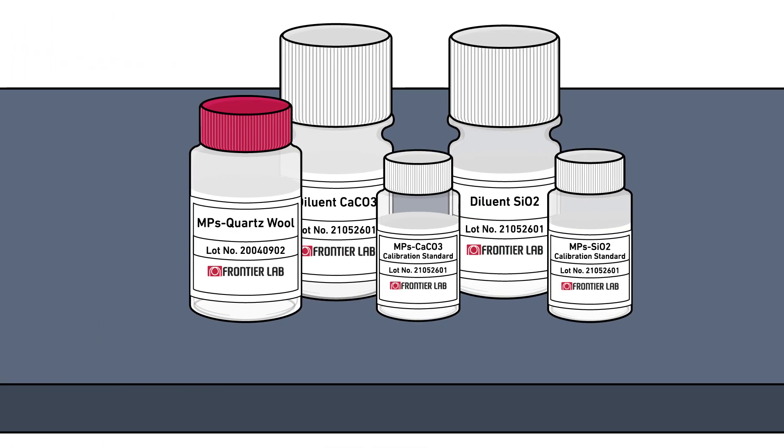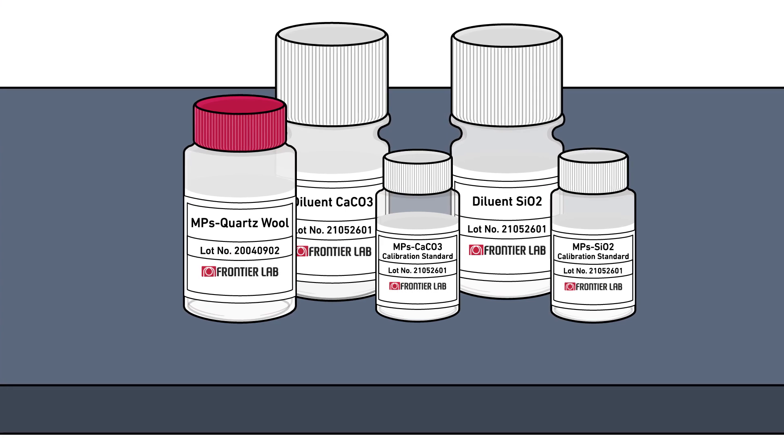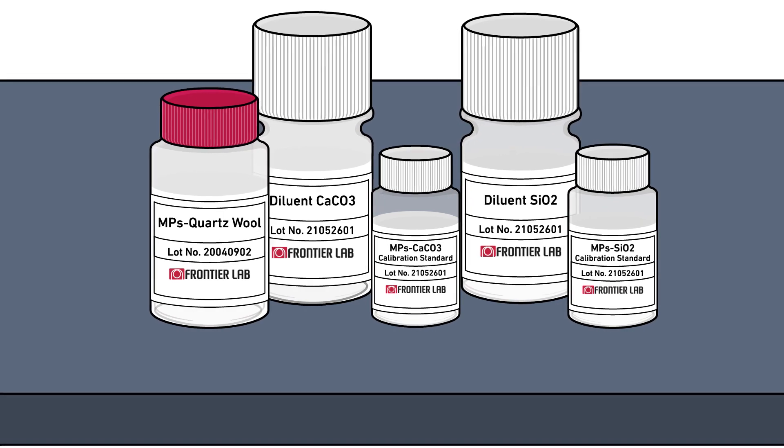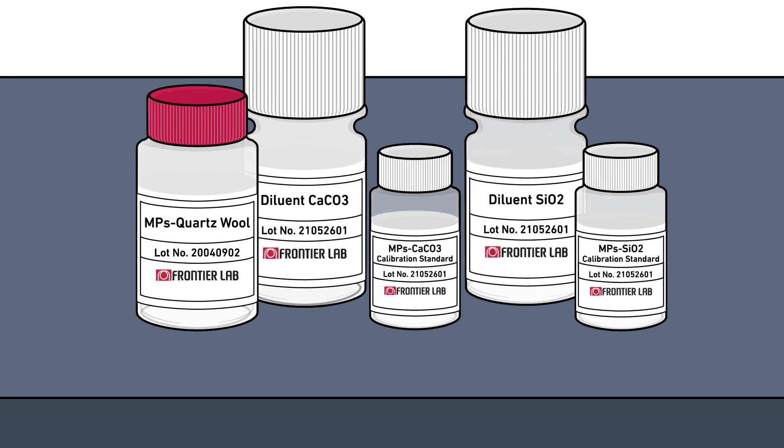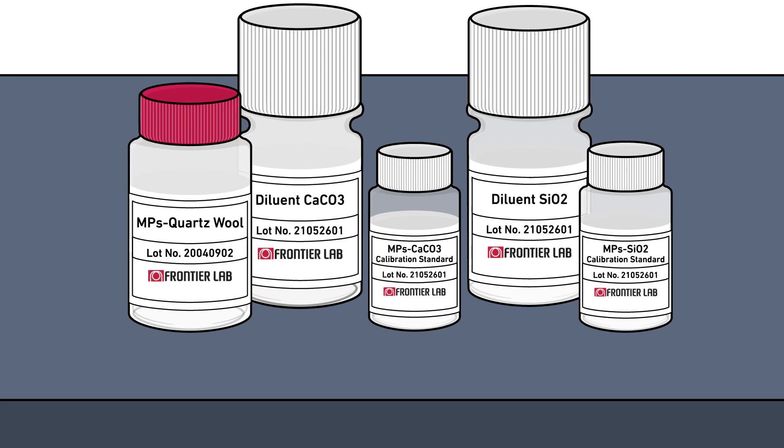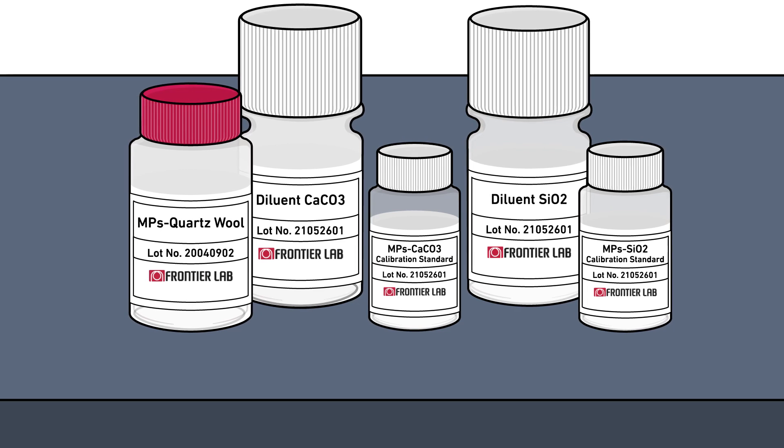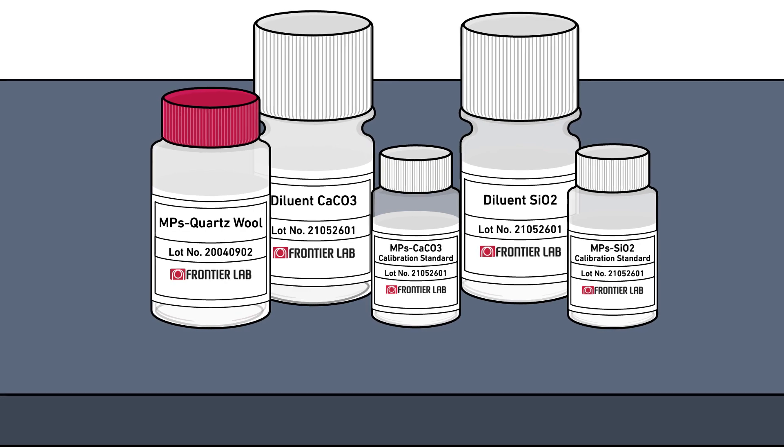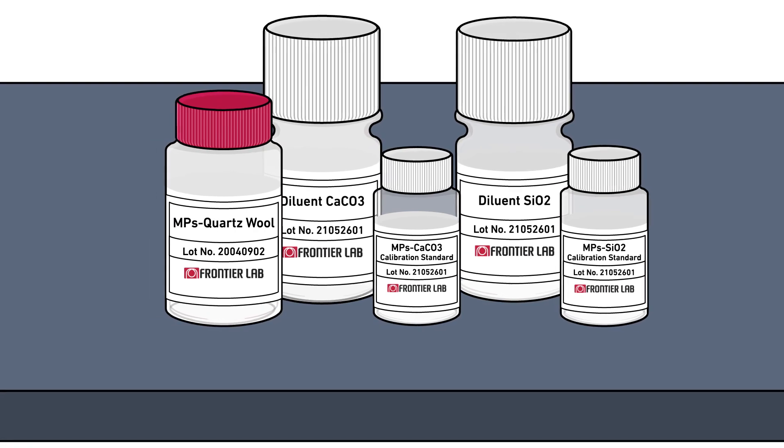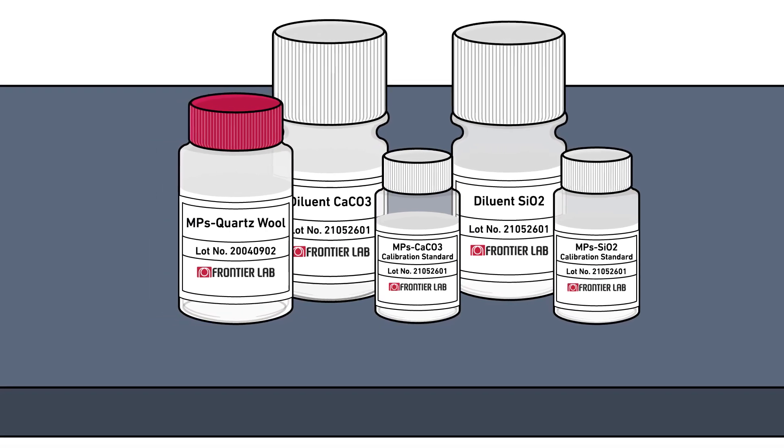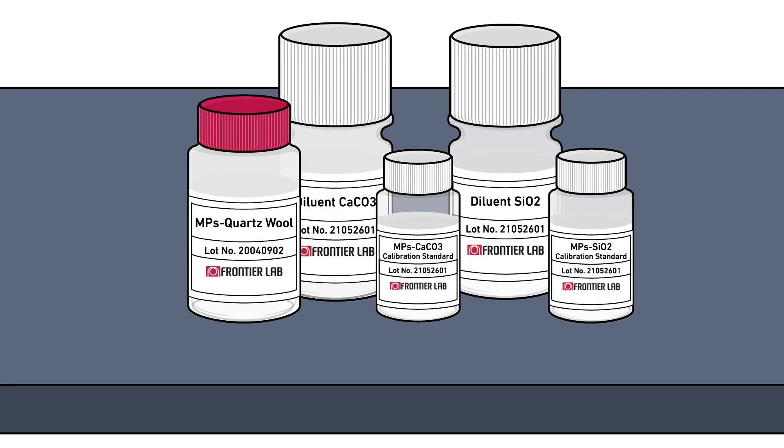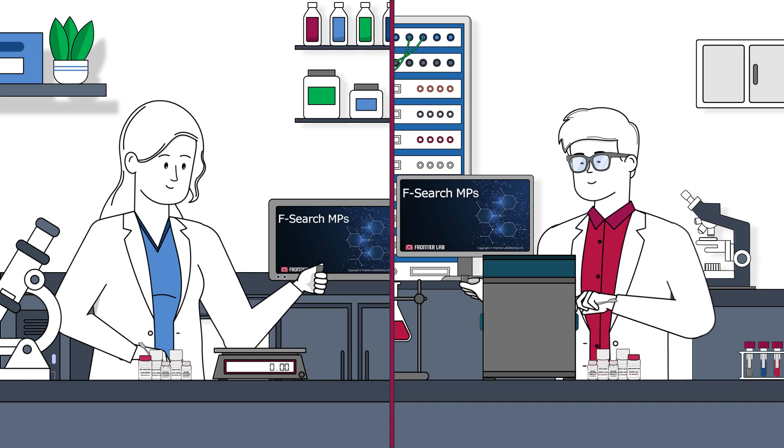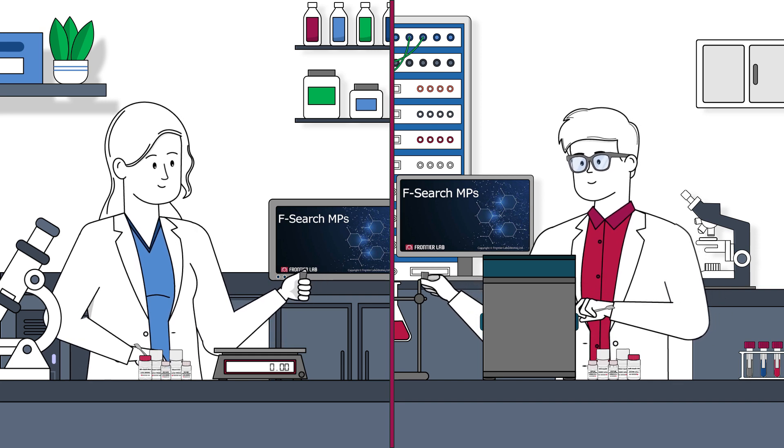Besides our Microfurnace Pyrolysis technology, our easy-to-use and comprehensive microplastics calibration standard kit sets our solutions apart from others. We offer two standards with different diluents, silicon dioxide or calcium carbonate. Both standards contain a few micrograms of each of the commonly used 12 polymers homogeneously dispersed in the diluent for easy weighing on semi-microbalances. But we also thought about laboratories that only have access to a regular balance.